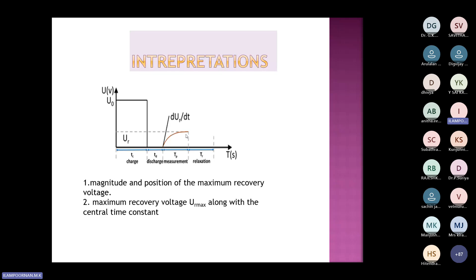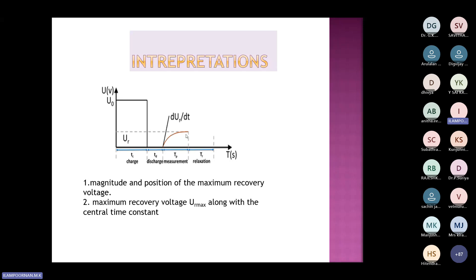These are all pure physics phenomena which has to be understood - if understood, better. But as an electrical engineer, to test the insulation, these two - the rate of rise and the peak of this return voltage - are sufficient to understand whether the insulation is working perfectly good or not. We need to take it at various levels of age, so this is also a kind of aging measurement.